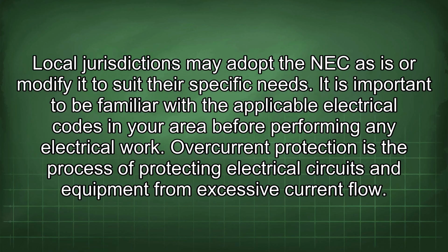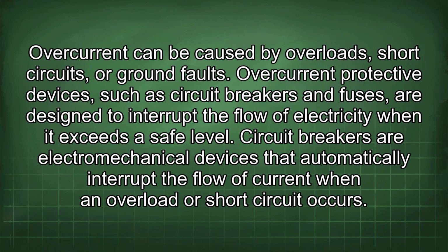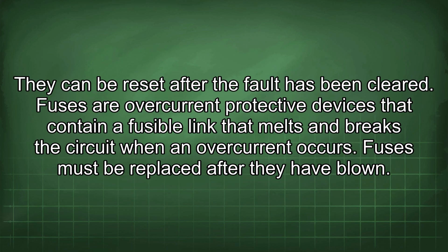Overcurrent protection is the process of protecting electrical circuits and equipment from excessive current flow. Overcurrent can be caused by overloads, short circuits, or ground faults. Overcurrent protective devices, such as circuit breakers and fuses, are designed to interrupt the flow of electricity when it exceeds a safe level. Circuit breakers are electromechanical devices that automatically interrupt the flow of current when an overload or short circuit occurs. They can be reset after the fault has been cleared.